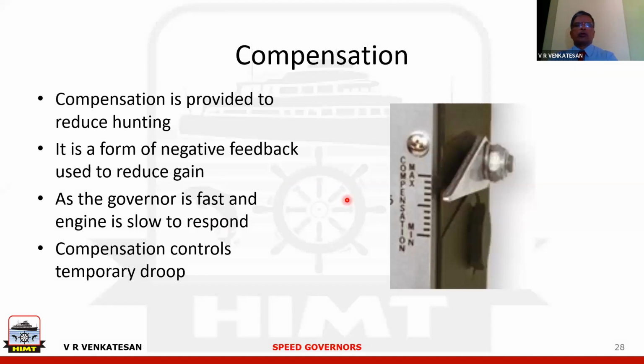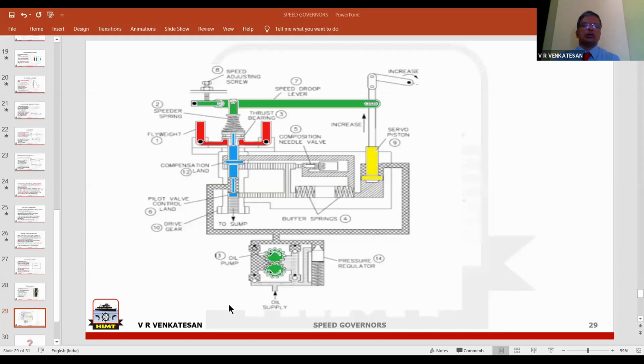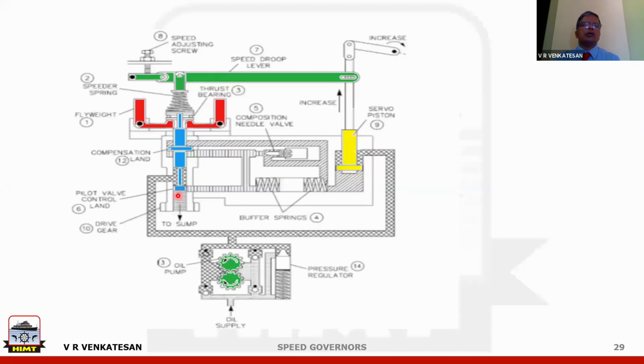So how do you provide compensation? The compensation is given this way. If you see this part, this is the hydraulic oil, this is a pilot valve. Output from the pilot valve is going to this part called the buffer piston and then to the power piston. But this oil is also allowed to come here, act on this part which is called a compensation land. So this is an additional part which is not there in the previous diagram.